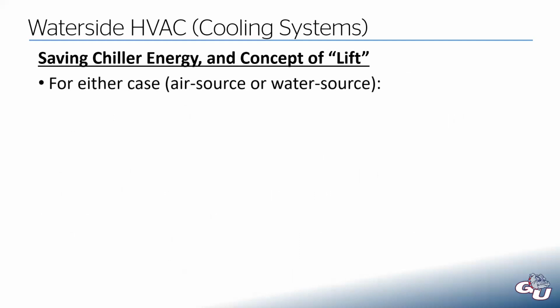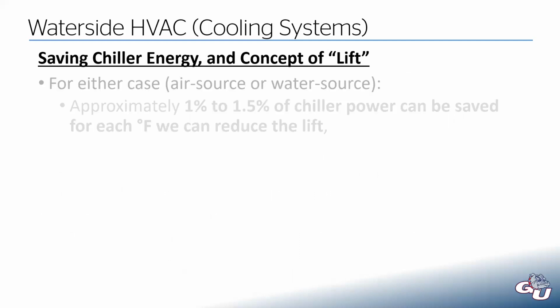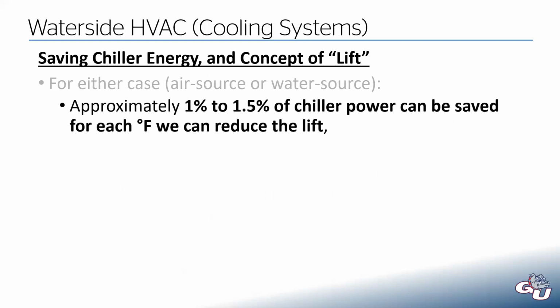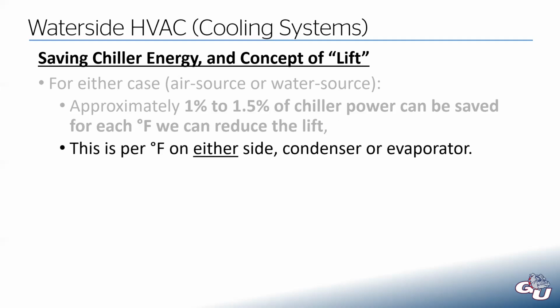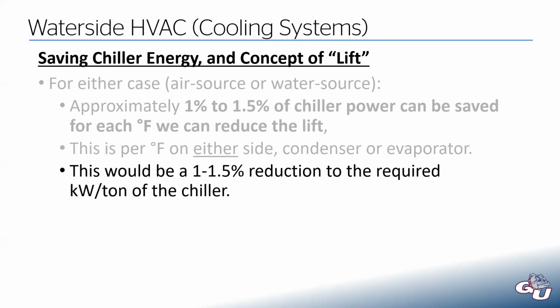For either case, whether it's air source or water source, we can save about 1 to 1.5% of chiller power for each degree Fahrenheit we can reduce the lift. And that is per degree on either side, whether that's the condenser temperature or the evaporator temperature. And that would be effectively a 1 to 1.5% reduction on the kW per ton of the chiller.